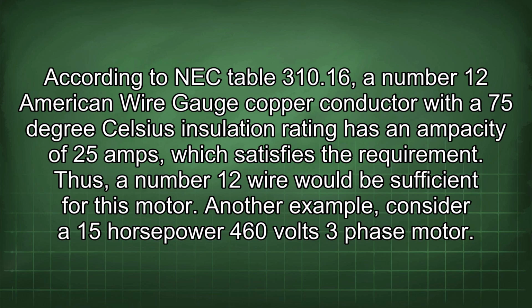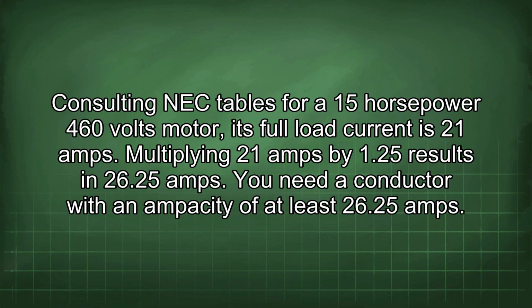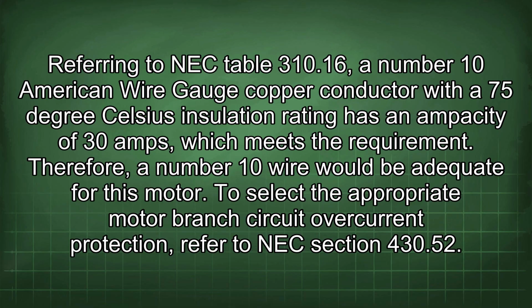Another example, consider a 15 horsepower 460 volts three-phase motor. Consulting NEC tables for a 15 horsepower 460 volts motor, its full load current is 21 amps. Multiplying 21 amps by 1.25 results in 26.25 amps. You need a conductor with an ampacity of at least 26.25 amps. Referring to NEC Table 310.16, a number 10 American wire gauge copper conductor with a 75 degrees Celsius insulation rating has an ampacity of 30 amps, which meets the requirement. Therefore, a number 10 wire would be adequate for this motor.